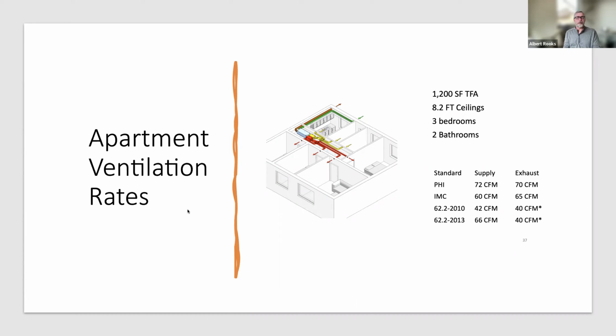And they're only different because Passive House would look at the exhaust and say, I need this much for a kitchen and I need this much for a bathroom. And that's really about pulling out excess humidity and smells and things like that. And on the 72 CFM side, it's looking at how many people we would typically put in this apartment, and it would be providing fresh air and trying to exhaust CO2 based on that, based on an occupancy rate, rather than how much moisture we make in bathrooms due to showers and things like that.